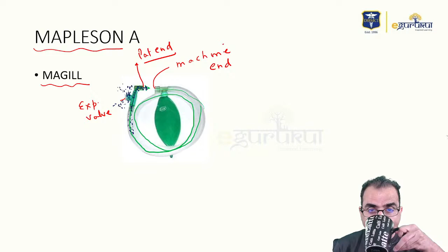So the aim of every circuit is that there should not be any rebreathing. Now, how to control this rebreathing? What they suggest is that you provide adequate fresh gas flow from the machine, so that these expiratory gases, due to the push of these gases, will first get vented out through the atmosphere and then the patient will receive the inspiratory gases.